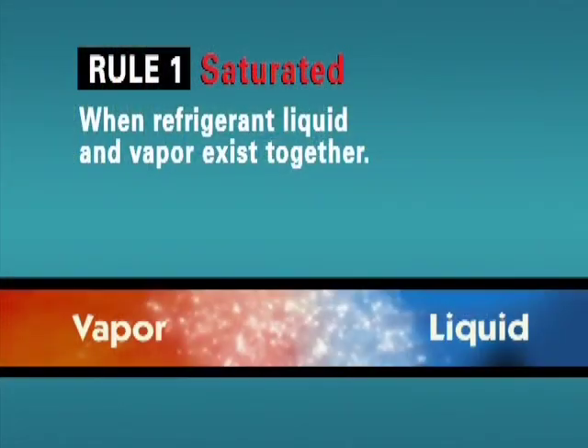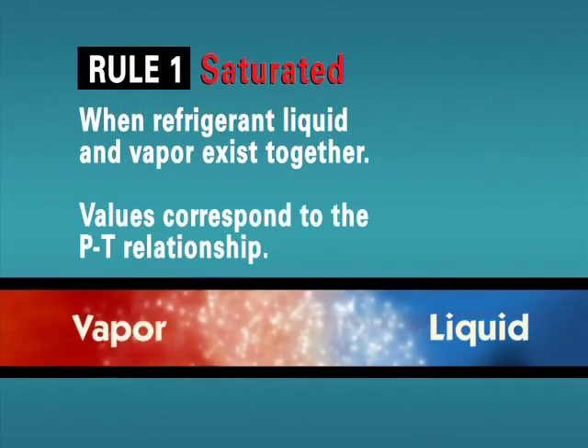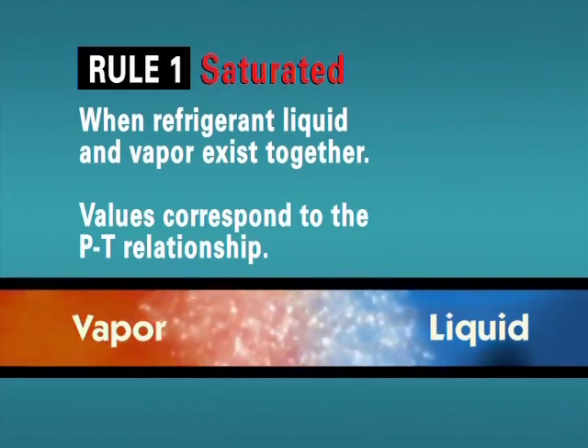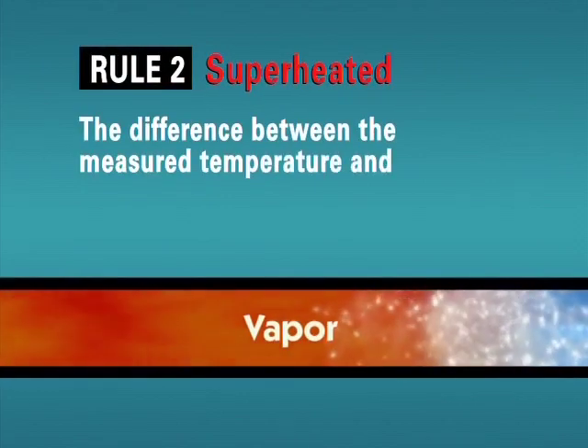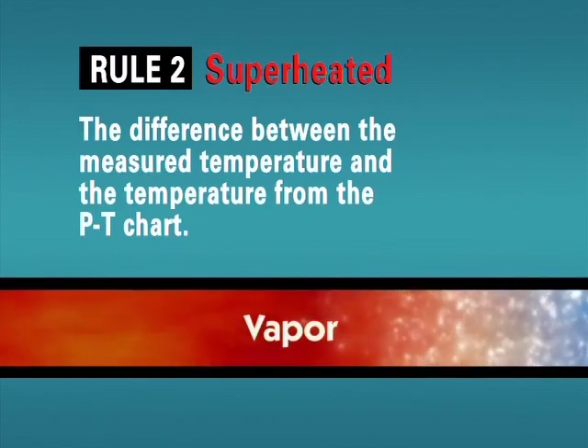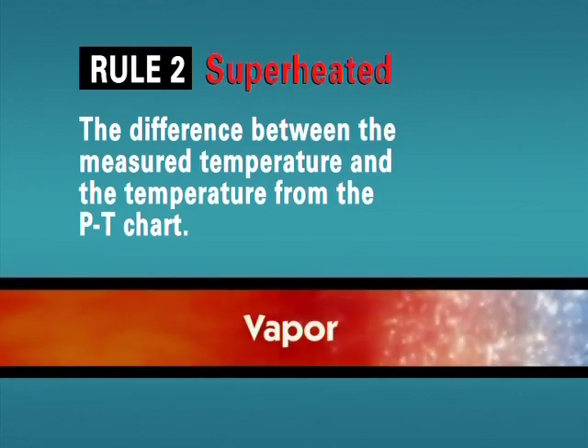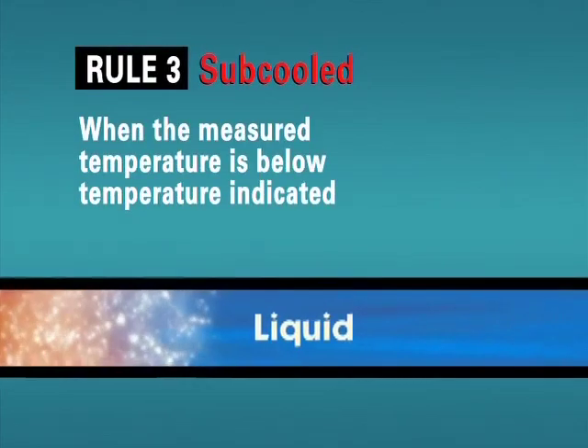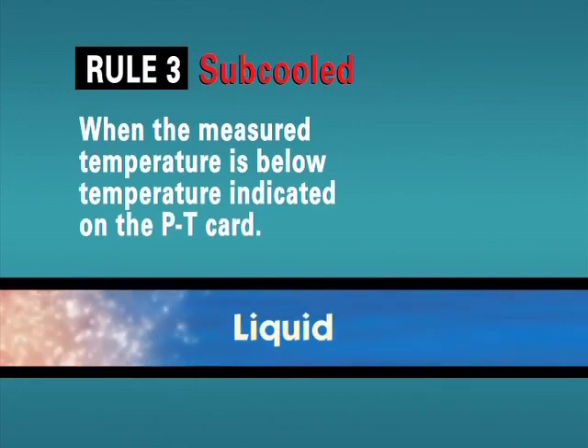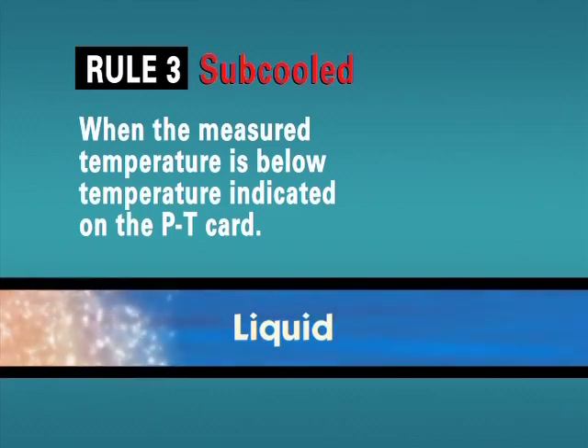So let's recap. There are three basic rules for determining the refrigerant condition in an operating system. Rule 1: When we have refrigerant liquid and vapor existing together, we have saturated refrigerant, and the pressure and temperature will correspond to our PT card. Rule 2: If our measured temperature is above the saturated temperature indicated on our PT card, we must have superheated vapor. The amount of superheat is the difference between our measured temperature and the saturated temperature. Rule 3: If our measured temperature is below the saturated temperature indicated on our PT card, we must have subcooled liquid. The amount of subcooling is the difference between our measured temperature and the saturated temperature. Understanding these rules, and knowing where these three conditions can occur, will enable you to use the PT card or the ChillMaster app as a vital tool in diagnosing system problems.